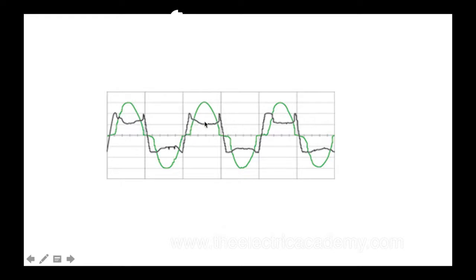The big difference is in the voltage waveform — first off, it's really noisy, a kind of skanky waveform. It's not nice and neat; it's got a lot of noise on it. Up here it's creating an arc, so that's where it jumps up, and on this half cycle it jumps up again. These are where the arcs are occurring and pushing the current across — at its highest, where the current is at its highest, is where the arc occurs. So this is what's happening when we have an arc fault.